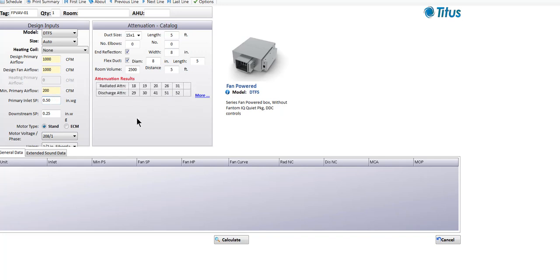A series fan box acts like a booster on the air handler because the air handler just has to deliver primary air flow to the inlet of the box, then the box fan picks it up and moves it the rest of the way to the room. That's a lot less work for the air handler than on a parallel box where the air handler has to move the air to the box, through the box, and all the way out to the room. Our downstream static pressure defaults to 0.25 inches — it's often less than a tenth of an inch because people tend to over-design their discharge ductwork, but I usually leave it at a quarter inch to make sure I'm covered.